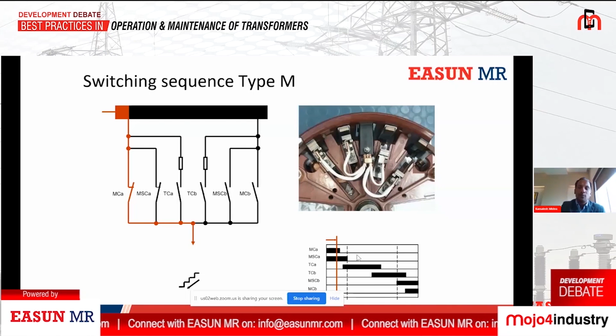Step by step, you can see the left side circuit representation. On the right side, there is the contact movement. This particular tap changer is for M type, but more or less this sequence is applicable for all types. Now we understand why maintenance is required. A contact has to move from one side to the other, basically with the help of many mechanisms: springs, copper braid, screw connections, energy accumulator.